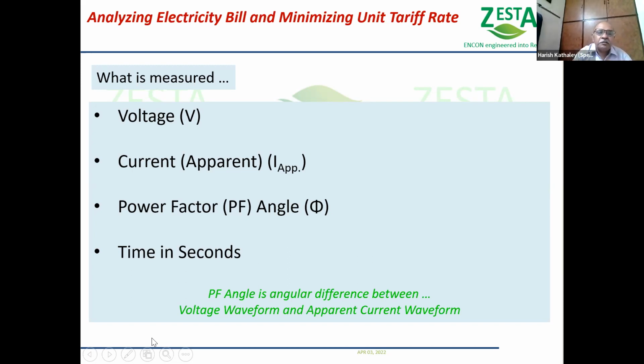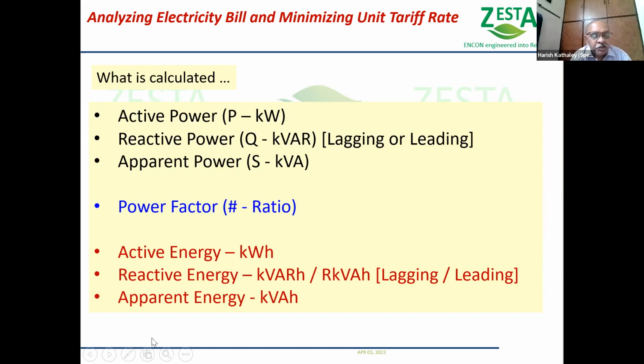But what is calculated? The calculations are done for active power, P is the symbol for active power, measured in kilowatts or megawatts depending on the quantum. Then reactive power, symbol Q, kVAR, lagging or leading, and apparent power symbol S, kVA. These three values are calculated. Then power factor, a ratio, kW by kVA, is calculated. Active energy kWh, reactive energy kVARH leading or lagging, and apparent energy - these values are not measured, they are calculated based on the measurement.